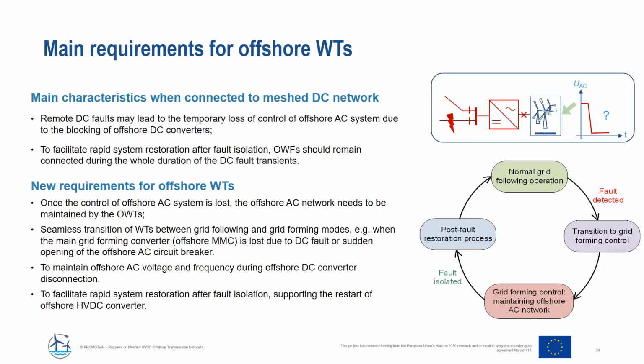When an offshore wind farm is connected to a mesh DC network, as previously seen, remote DC faults may lead to the temporary loss of control of the offshore AC system due to the blocking of offshore DC converters. Therefore, to facilitate rapid system restoration after fault isolation, offshore wind farms should remain connected during the whole duration of the DC fault transient. This adds a significant new requirement for offshore wind turbines. Once the control of the offshore AC system is lost, the offshore AC network needs to be maintained by the offshore wind turbines.